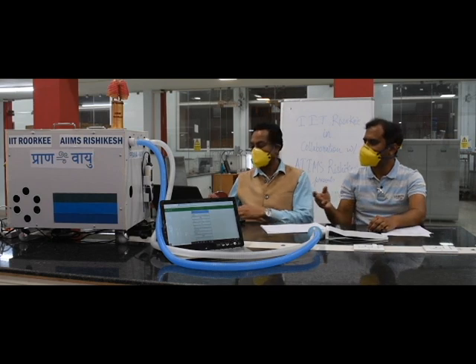For tidal volume, we'll be keeping 400 cc. Respiratory rate will be 15. Inspiration to expiration will be 1:2. Trigger will be set at -2 centimeter of water column, and pressure support will be given up to 10 centimeter of water column. Let me set the system accordingly. The Pranvayu ventilator will be set in that mode.